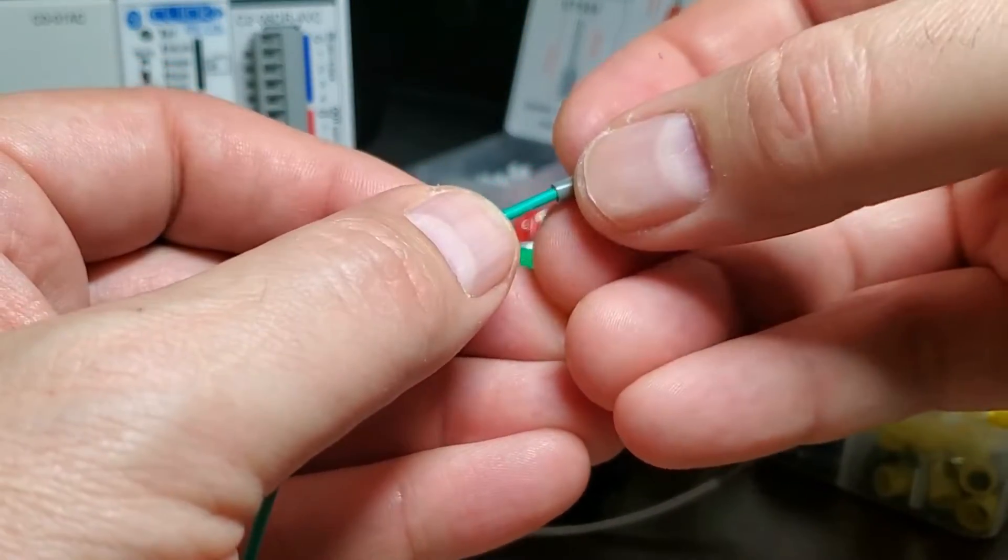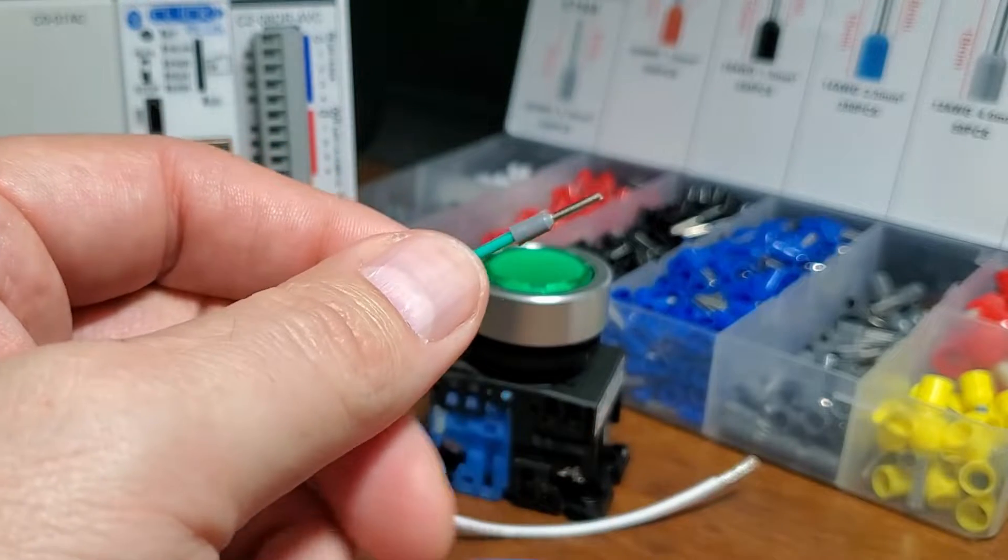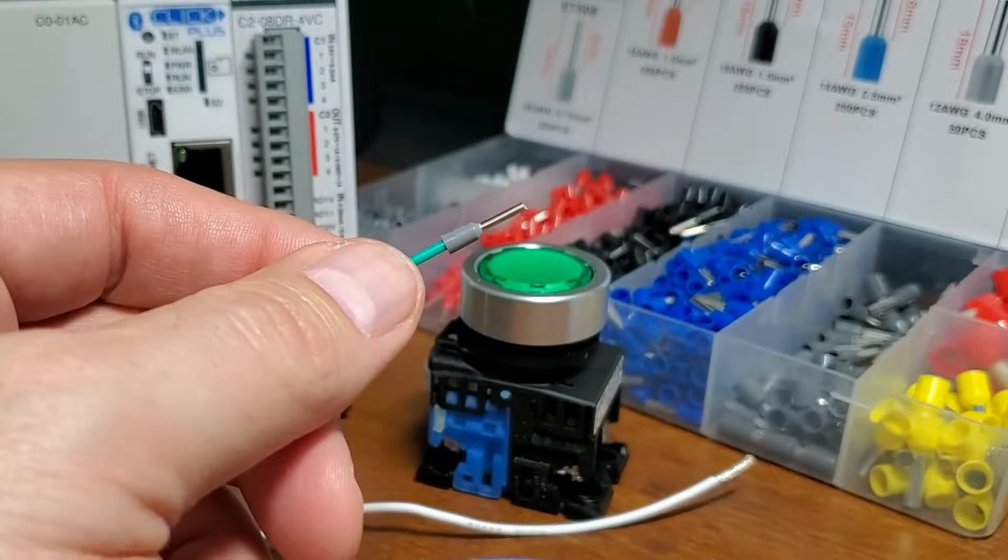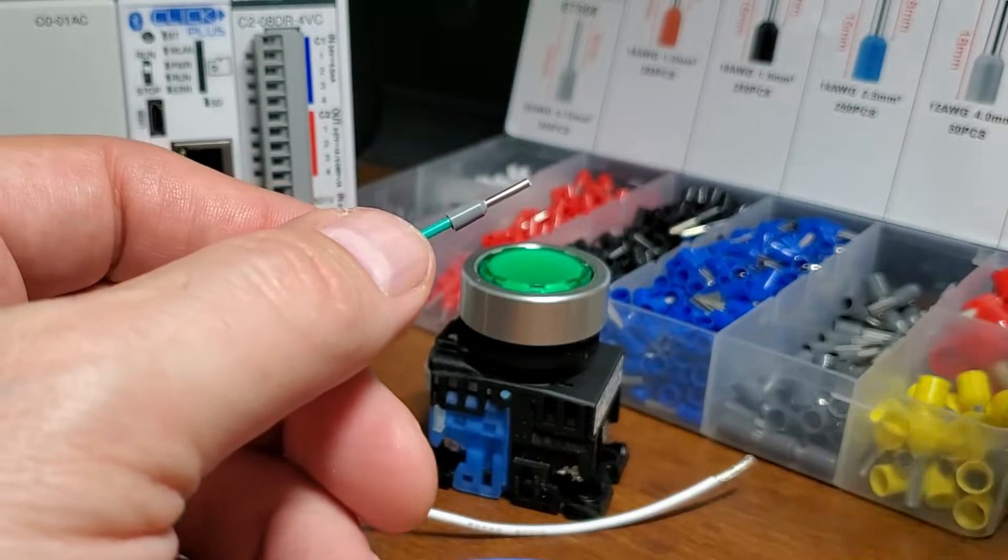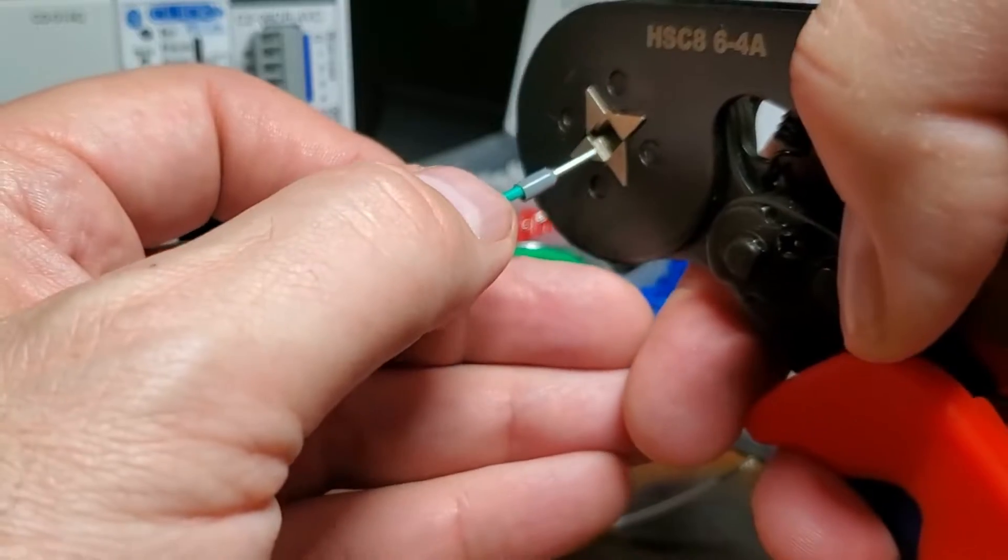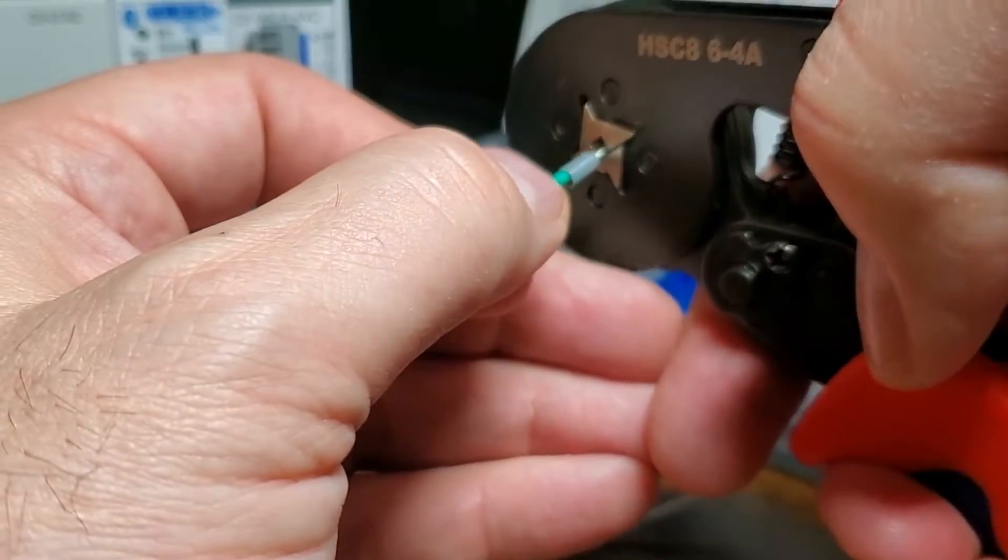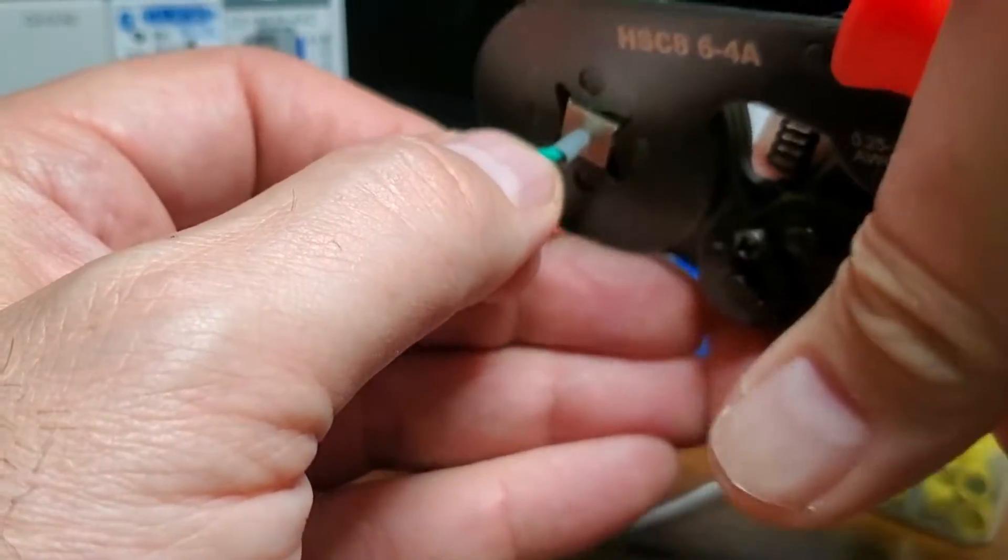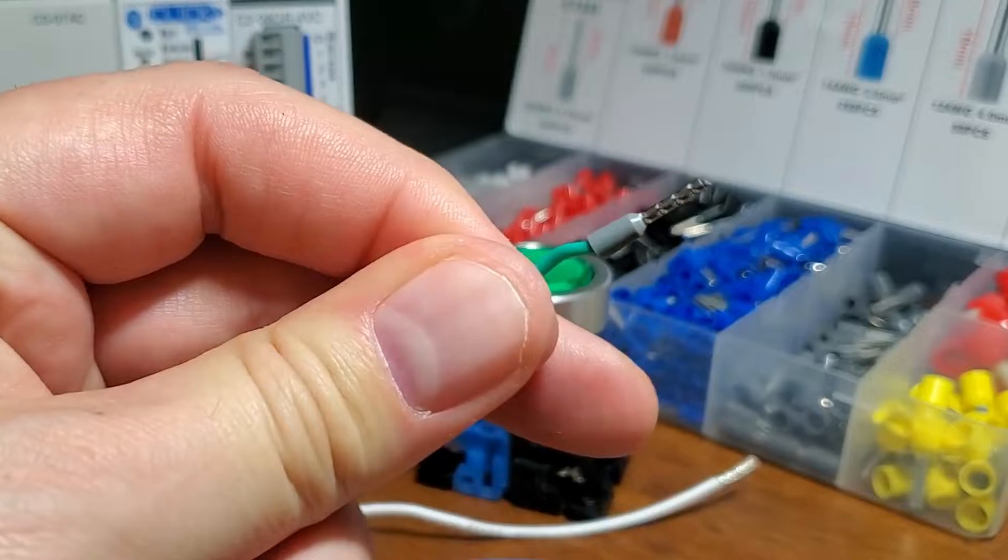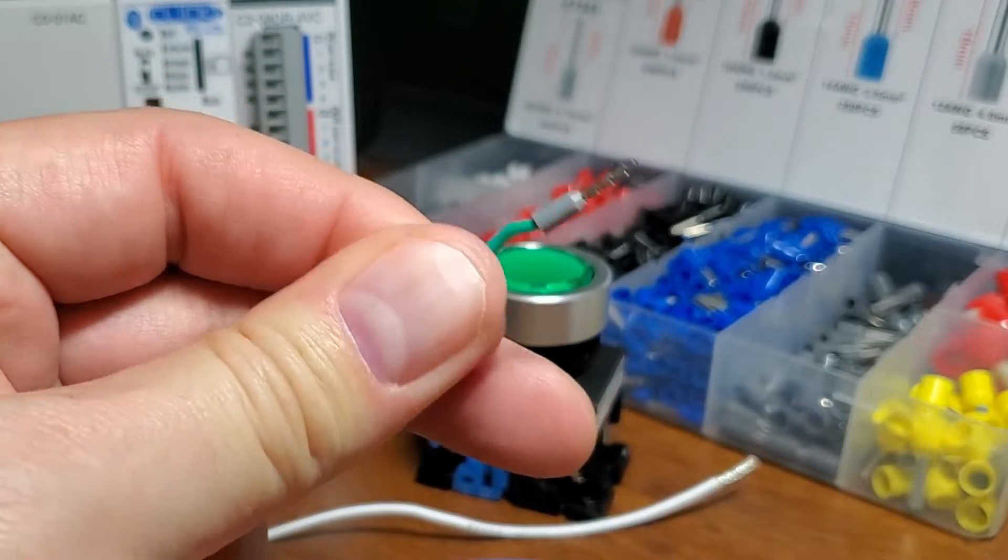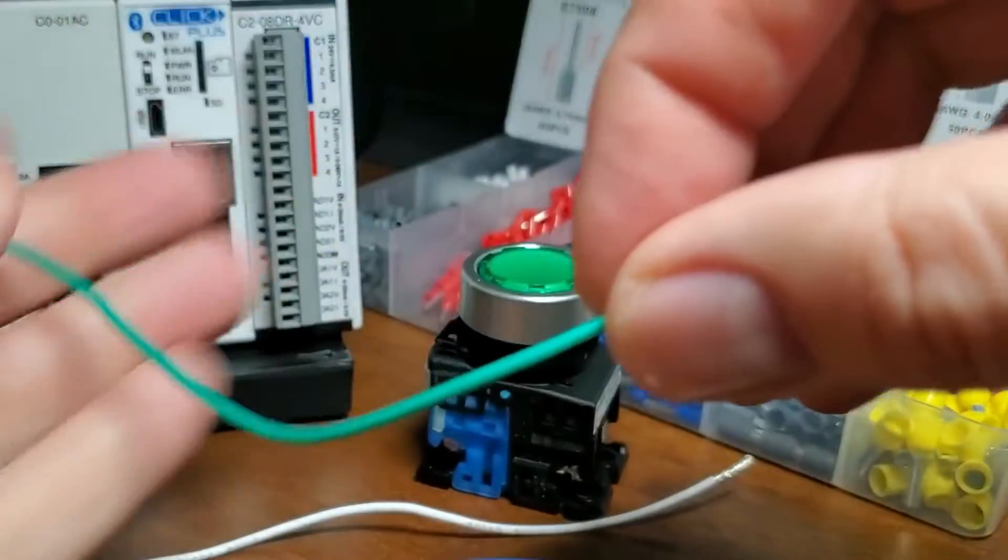There are two different ways to connect the stranded copper wire to terminals. Using a soldering iron and tinning the stripped ends of the wire will keep the stranded wire together for the connection. However, this takes more time and is less neat and convenient than a ferrule.